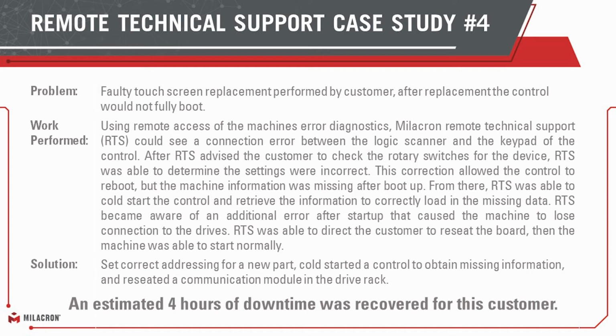Something got bumped, which caused a loose connection, and suddenly the machine's pumps wouldn't start. With that, we were able to identify it was this drive. We looked in and could see the communication was missing here. We recommended reseating that drive, and luckily that got the machine up and running again.